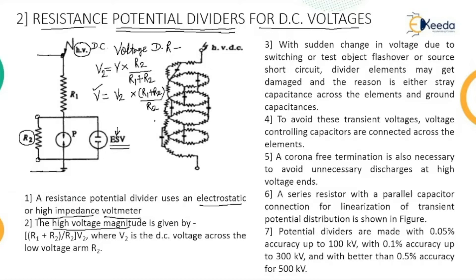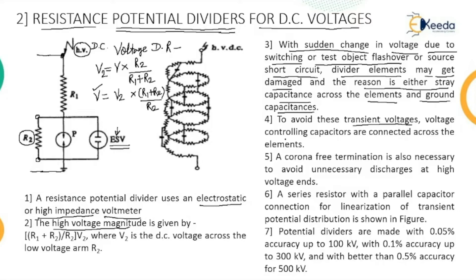With a sudden change in voltage due to switching, whenever switching takes place, or if the test object flashes over or the source is short-circuited, the divider elements may get damaged. The reason is either stray capacitance across the elements or ground capacitances. To avoid this flashover, transient voltage-controlling capacitors are connected across the elements. A corona-free termination is also necessary to avoid unnecessary discharge at high voltage range.